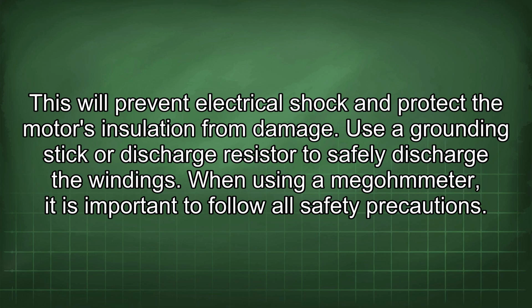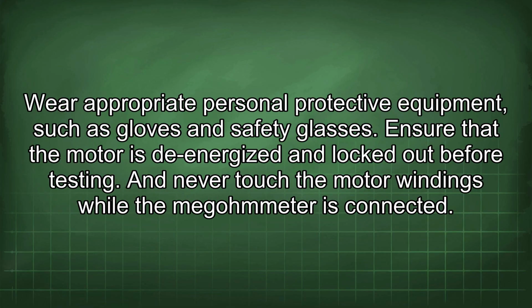When using a megohmmeter, it is important to follow all safety precautions. Wear appropriate personal protective equipment, such as gloves and safety glasses. Ensure that the motor is de-energized and locked out before testing. And never touch the motor windings while the megohmmeter is connected.